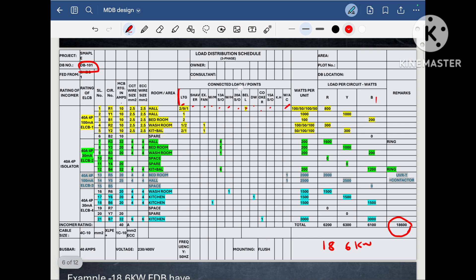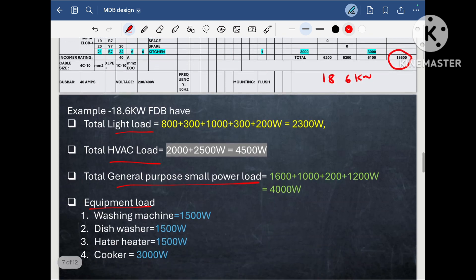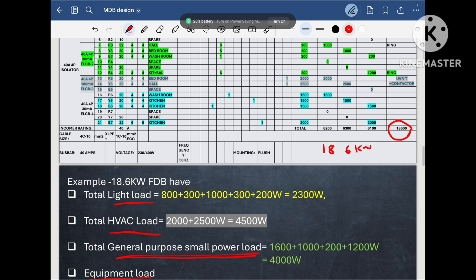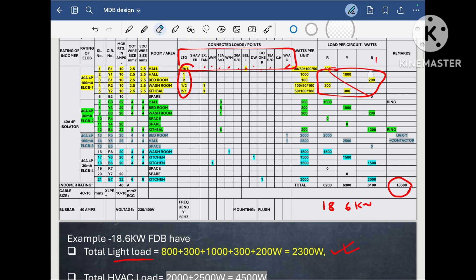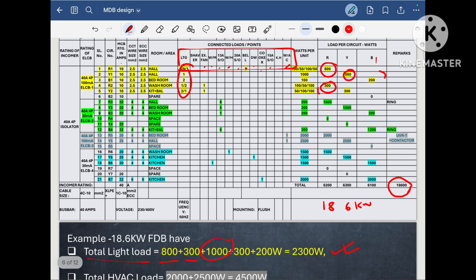When we categorize this load, we can divide it into four parts: light load, HVAC load, general purpose load, and equipment load. I distributed all the loads accordingly. The light load includes loads of 800 Watt, 300 Watt, 1000 Watt, 300 Watt, and 200 Watt — so the total light load is 2300 Watt.